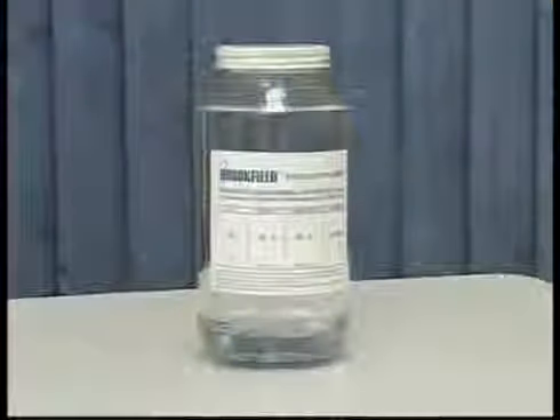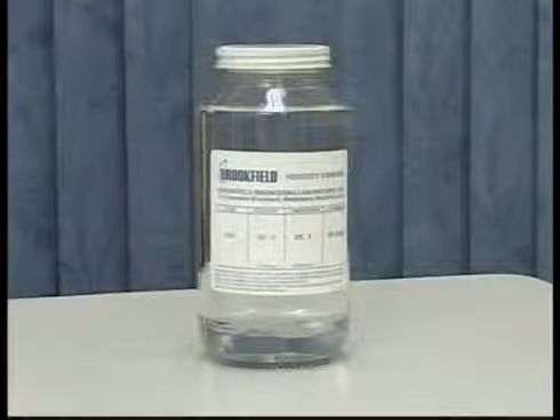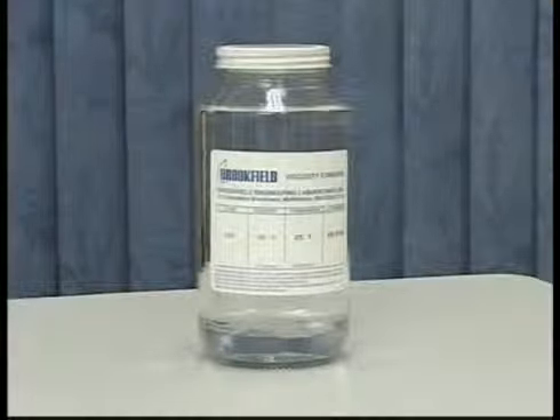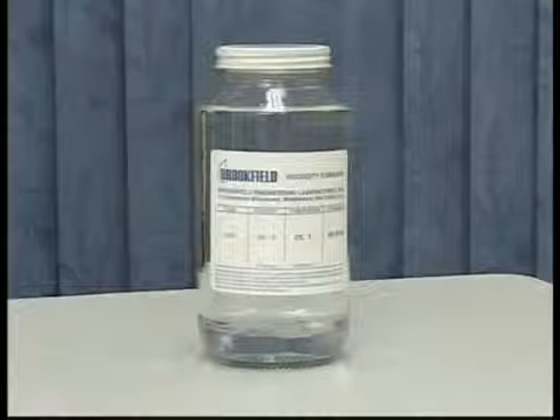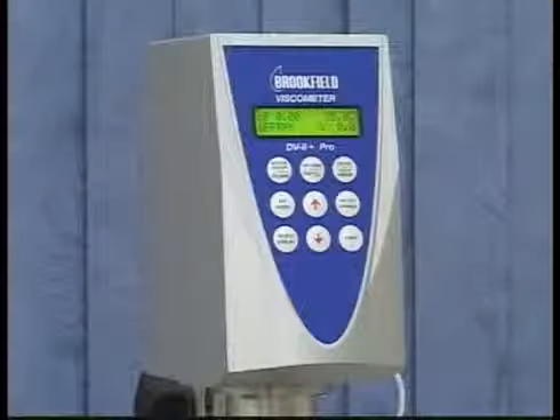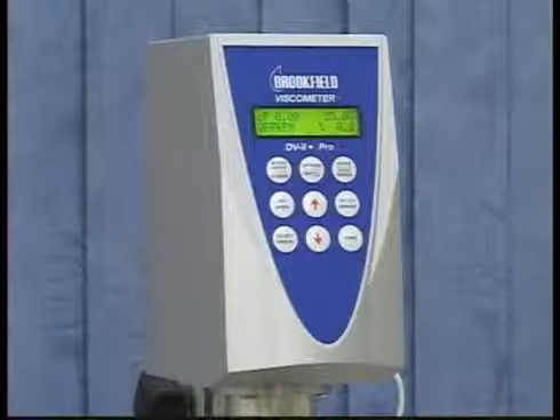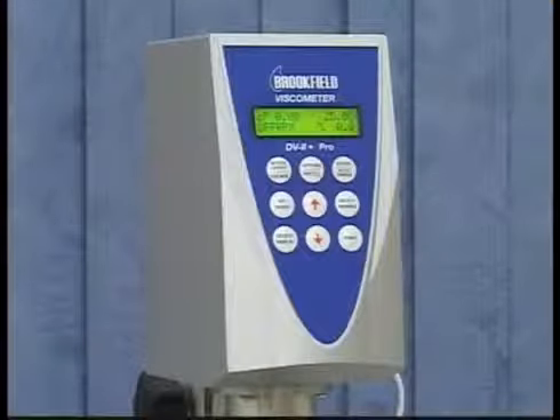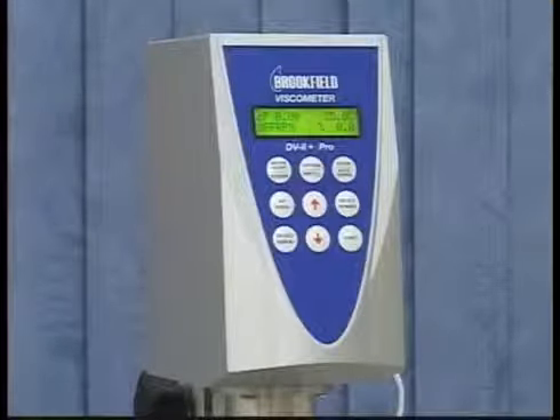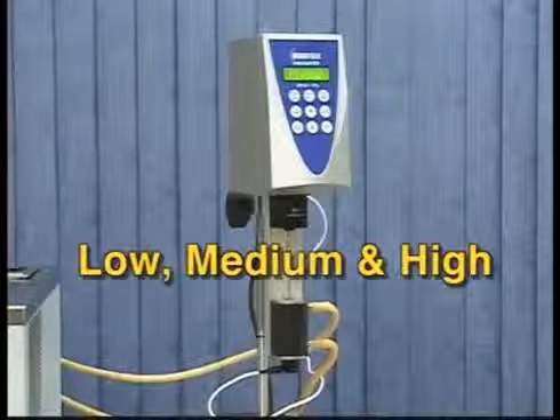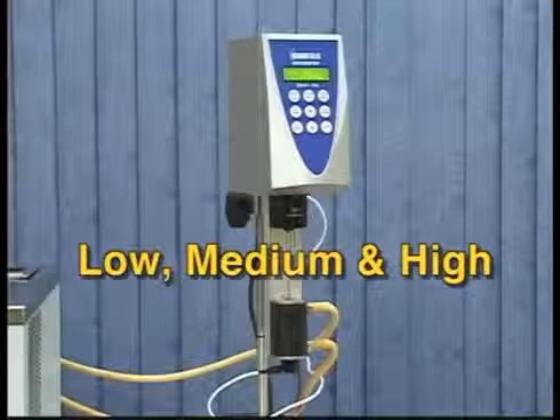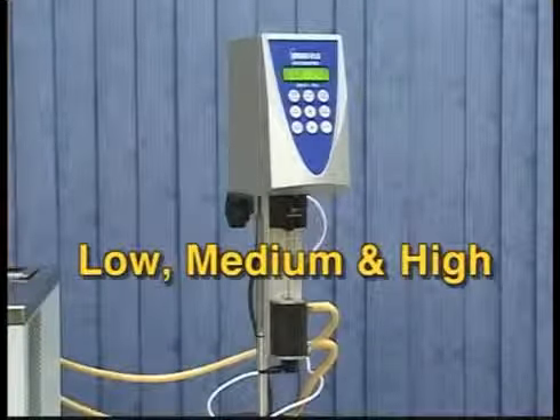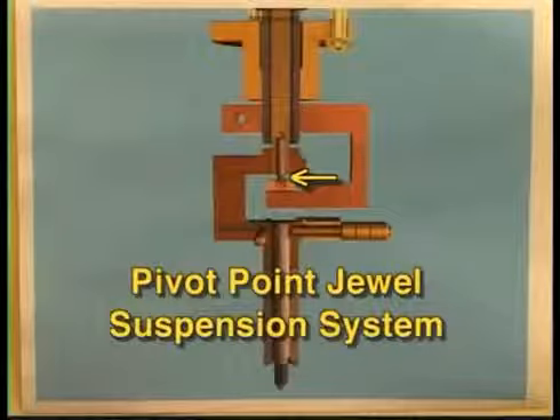You do not need to select a fluid based on the material you will be testing. However, many customers choose to do so as a simple verification check. The calibration routine checks the linearity of the spring on the instrument by using one fluid at 3 separate speeds to achieve low, medium, and high torque ranges. This checks the linearity of the spring and the sensing mechanism of the instrument.